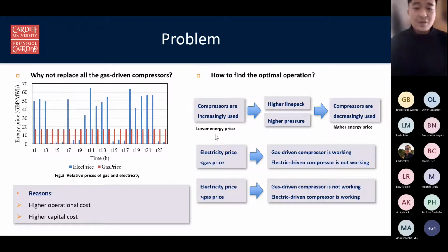So at this stage, we hope we can find the optimal operation of compressor units that can reduce emissions and save cost as well. But how can we achieve this? We can use line pack as a lever. When energy price is lower, we can increasingly use the compressor units to raise the level of line pack and hence raise the pressure as well. And when energy price is higher, the compressor unit is not required to work as hard, as the pressure has already been increased.